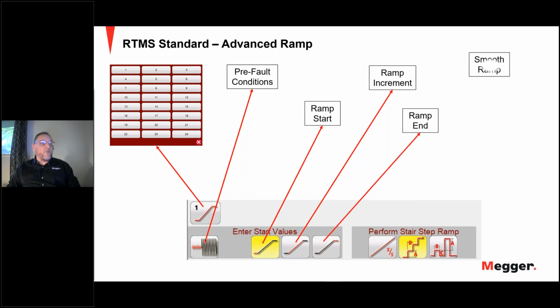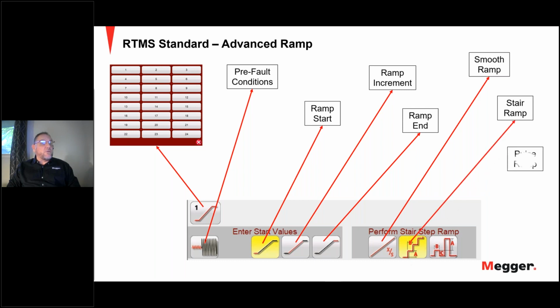The different types of ramps that can be performed include a smooth ramp, and the smooth ramp will output by applying a value based upon entry of an increment value over a time period. Then you've got the stair ramp, and lastly the pulse ramp.